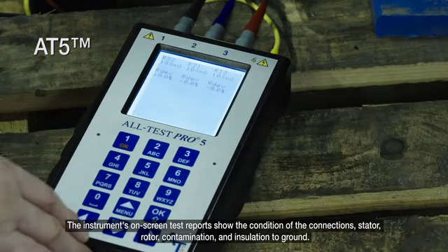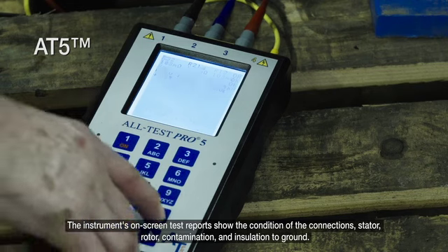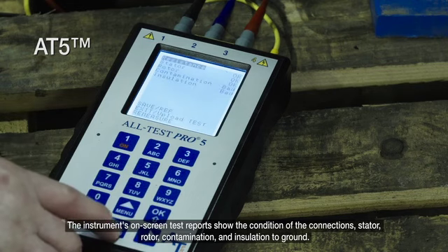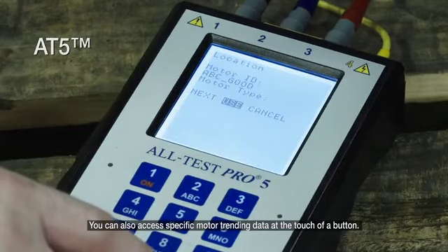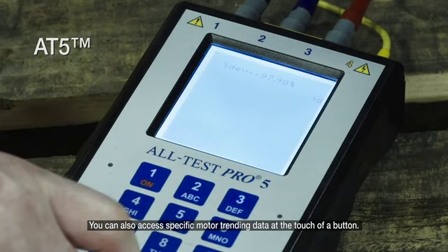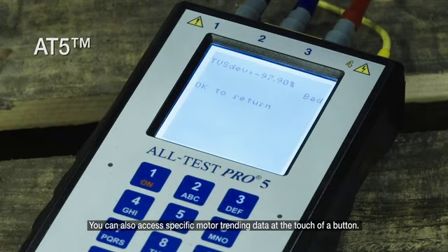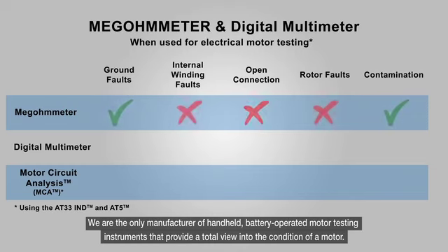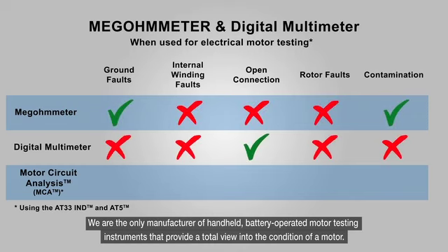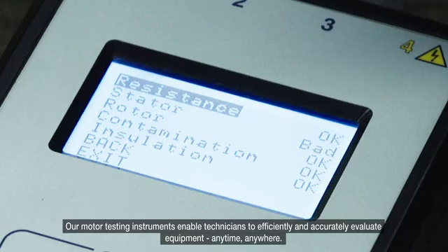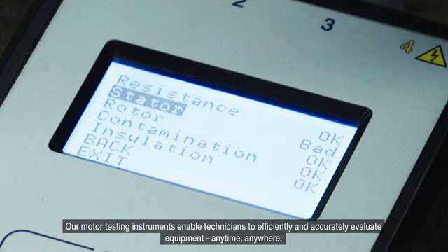The instrument's on-screen test reports show the condition of the connections, stator, rotor, contamination, and insulation to ground. You can also access specific motor trending data at the touch of a button. We are the only manufacturer of handheld, battery-operated motor testing instruments that provides a total view into the condition of the motor. Our motor testing instruments enable technicians to efficiently and accurately evaluate equipment anytime and anywhere.